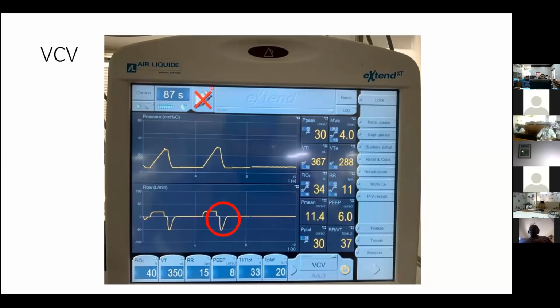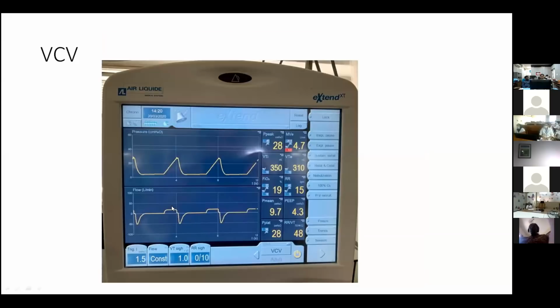Now coming to the flow. This is the constant flow which we are routinely using, and if you want to understand patient-ventilator asynchrony, better you use this mode because our eyes are usually trained for this flow pattern. This is the inspiratory trigger. The inspiratory trigger is the pressure which, when the patient's body achieves a particular level, the ventilator will start helping or assisting the patient. So you can keep your inspiratory trigger around 2. Here it is 1.5. This trigger can be a pressure trigger or a flow trigger. In present day ventilators, there is hardly any difference if you use pressure or flow. They are more or less the same.